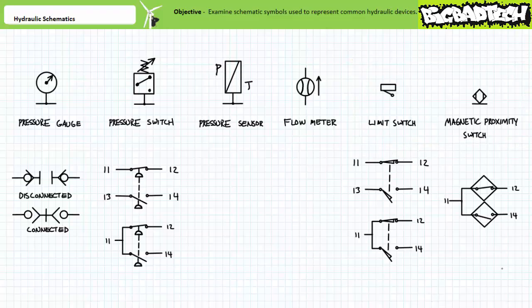Again, given both limit and magnetic proximity switches are point of interaction between the hydraulic and electrical aspects of an electrically controlled system, the same switches will also have an associated electrical schematic symbol. Here's the electrical schematic symbol for a mechanically interlocked pair of single-pole, single-throw limit switches, one being normally closed, the other being normally open. Alternatively, some limit switches use single-pole double-throw transfer contacts, with both the normally closed and normally open side being serviced by a single common terminal.